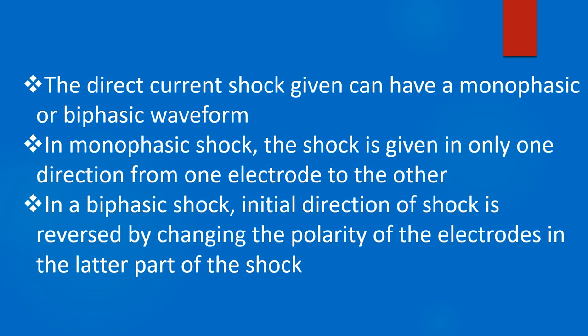The direct current shock given can have a monophasic or biphasic waveform. In a monophasic shock, the shock is given in only one direction from one electrode to the other. In a biphasic shock, the initial direction of shock is reversed by changing the polarity of the electrodes in the latter part of the shock.